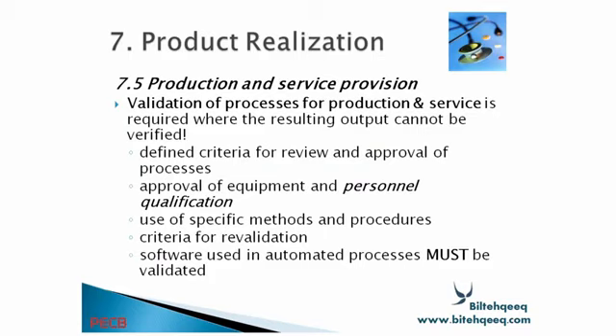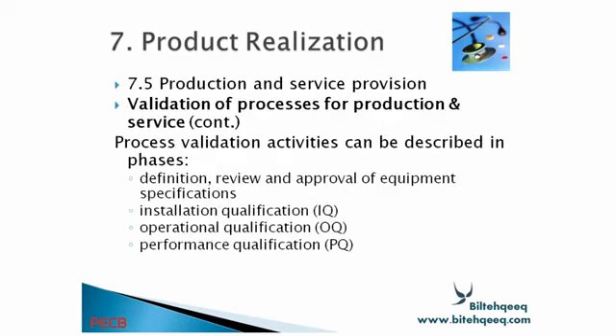Validation of processes for production and service is required where resulting output cannot be verified. In some processes, you are unable to verify the output during the process, so for these kinds of processes you have to perform validation. You must define criteria for review and approval of the process, approval of equipment and personnel qualifications, use of specific methods and procedures, criteria for re-validation, and software used in automated processes must be validated. Process validation activities can be described in phases: definition, review and approval of equipment specifications, installation qualification, operational qualification, and performance qualification.